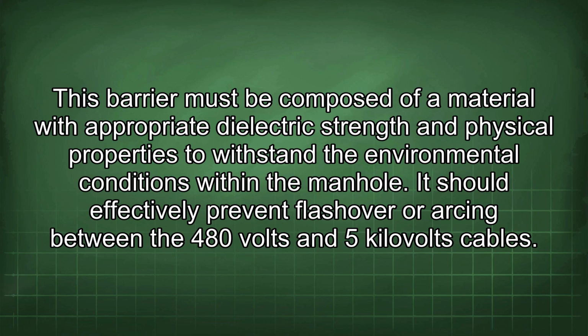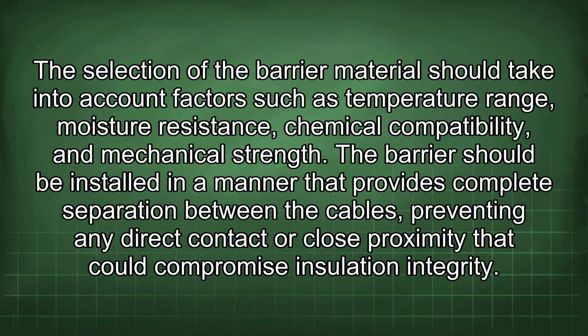This barrier must be composed of a material with appropriate dielectric strength and physical properties to withstand the environmental conditions within the manhole. It should effectively prevent flashover or arcing between the 480 volts and 5 kilovolts cables. The selection of the barrier material should take into account factors such as temperature range, moisture resistance, chemical compatibility, and mechanical strength. The barrier should be installed in a manner that provides complete separation between the cables, preventing any direct contact or close proximity that could compromise insulation integrity.